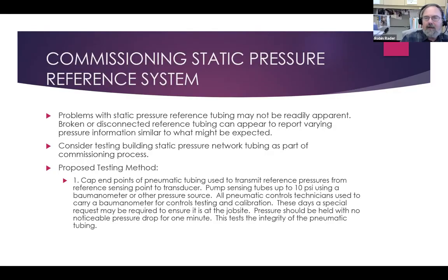This could be done simply by putting plugs at the end of the static pressure references. That way you get out there and you actually see where they put these references. So you put plugs into the ends of the static pressure references, and then you blow the pneumatic tubing up, close off pressure, and just see that it maintains pressure. So it's pretty easy to test.